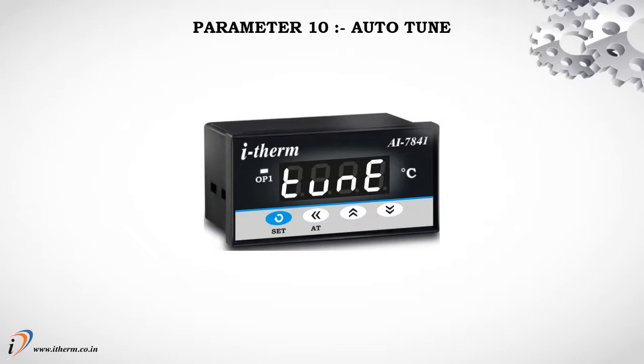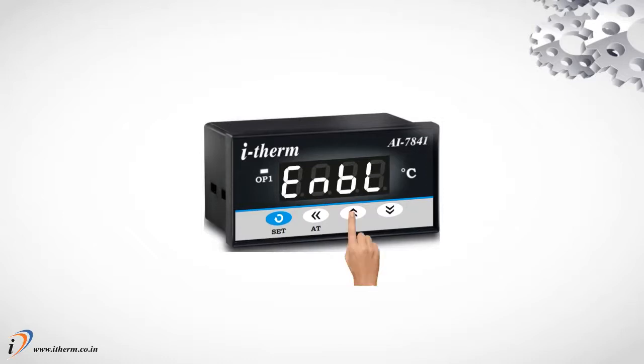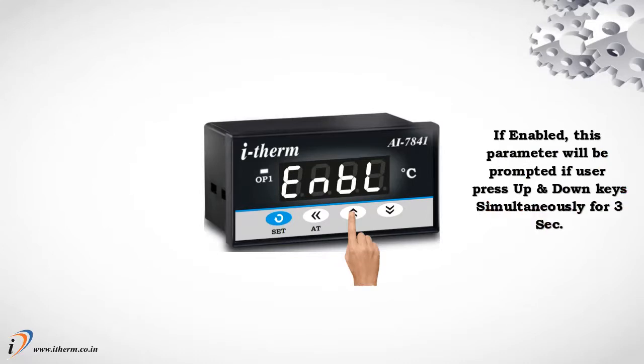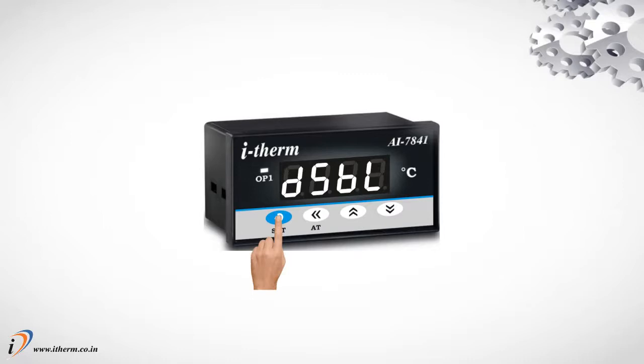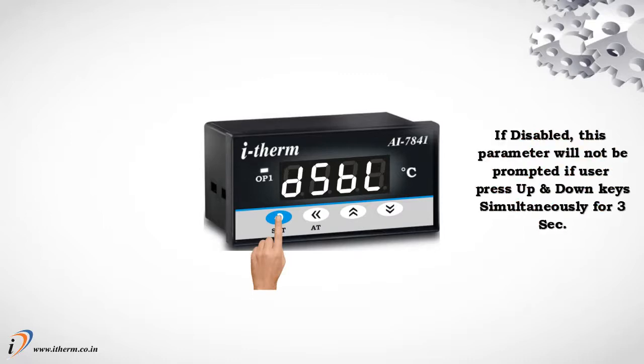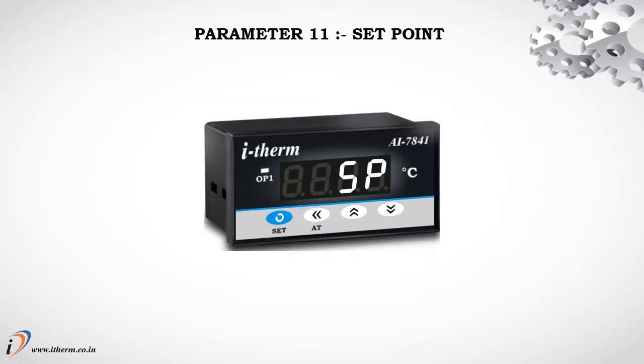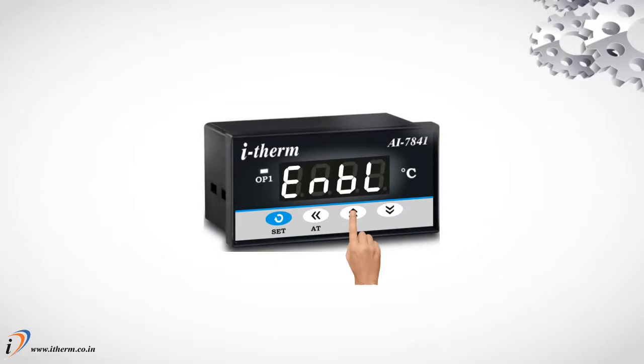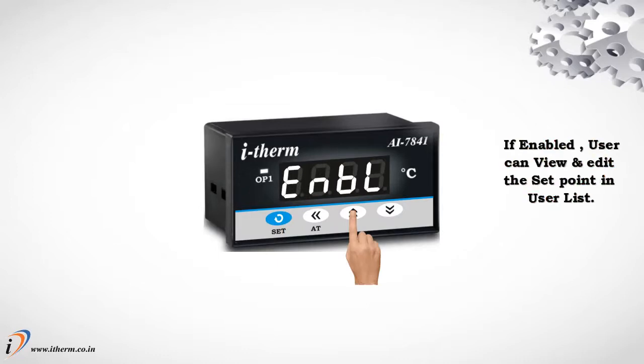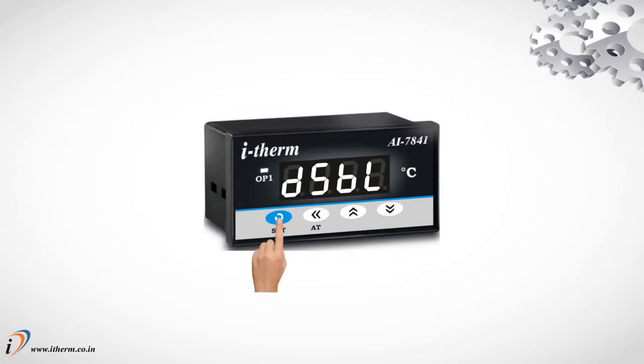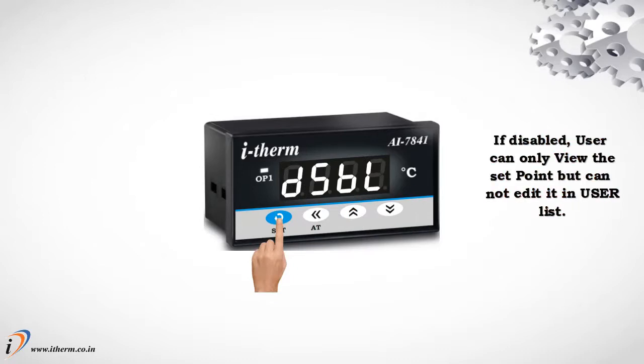Parameter 10, Auto tune. If enabled, this parameter will be prompted if user presses up and down keys simultaneously for 3 seconds. If disabled, this parameter will not be prompted if user presses up and down keys simultaneously for 3 seconds. Parameter 11, Set point. If enabled, user can view and edit the set point in user list. If disabled, user can only view the set point but cannot edit it in user list.